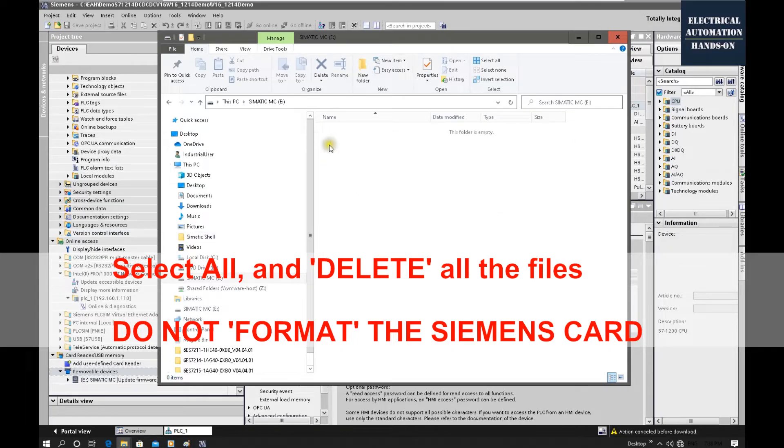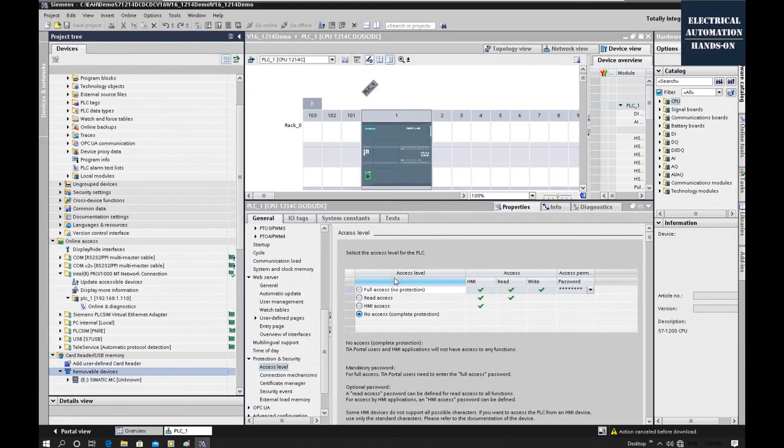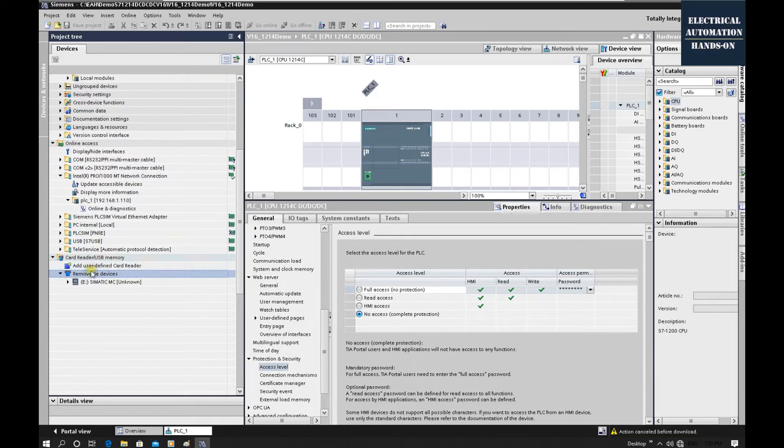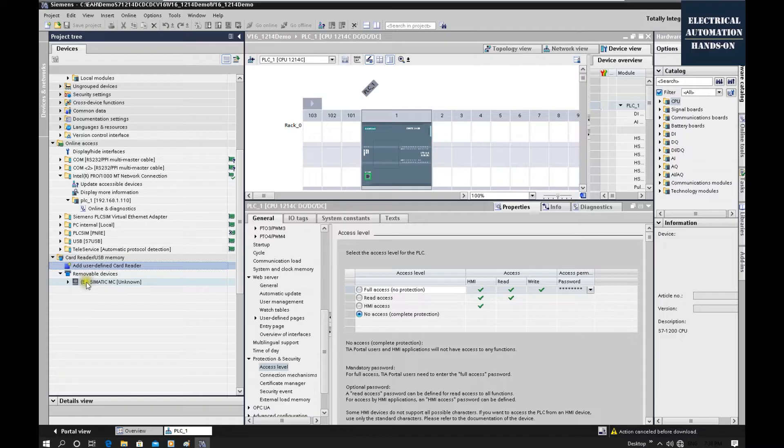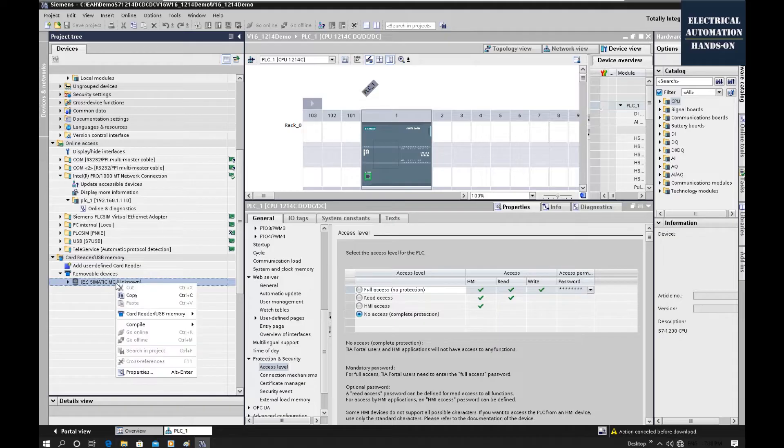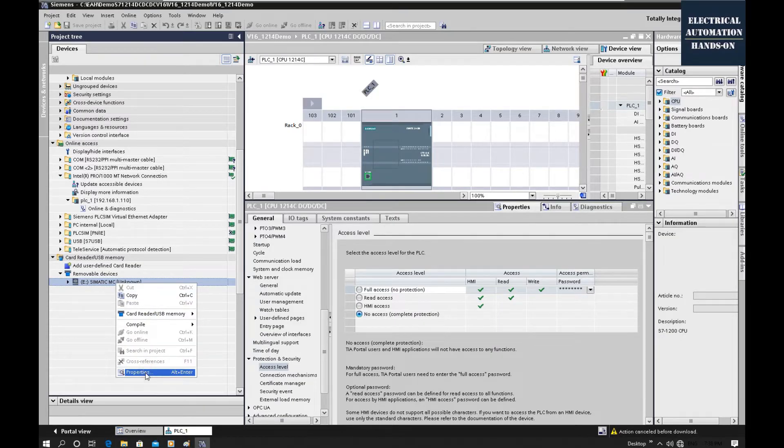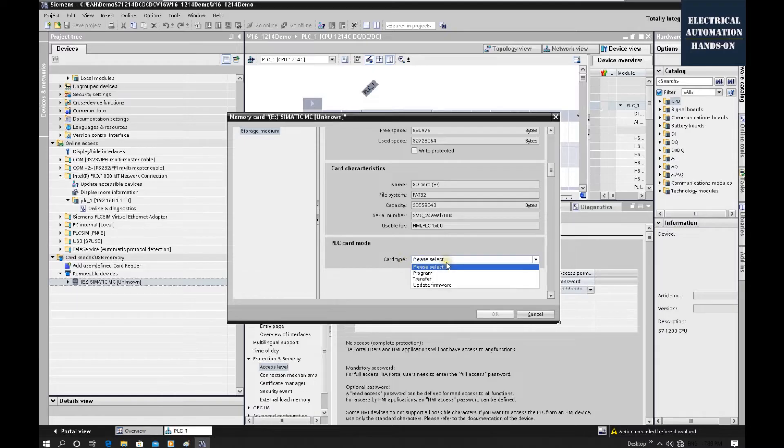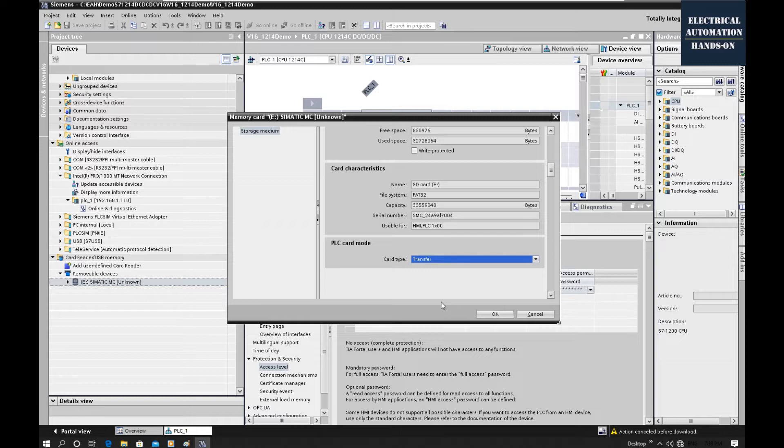After we delete this memory card, then go back to the TIA portal. From the left side, go down here, the card reader here. And your system will identify this memory card. And from here, you can right click, click this properties. And here you need to select the card type. Now I need to select the transfer. Set up the transfer card type.